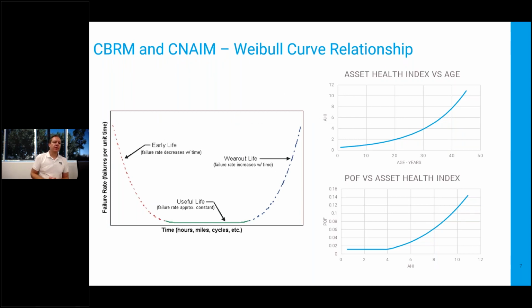The health index has a well-defined mathematical relationship to the probability of failure via certain constants -- K values, C values, and the HI limit. But where does this relationship between asset health index and probability of failure come from? Well, it's derived from the Weibull failure curve.